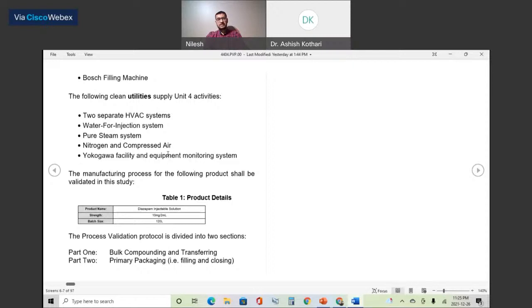This is Yokogawa, the name of the software which monitors 24/7, 365 days, the differential pressure and environmental conditions like humidity, temperature, nitrogen gas pressure, compressed air pressure, everything. Every time you log in, for each 3 seconds you get the results. So if something is out of spec, like temperature not in control, you get an alarm and your machine automatically stops. It will not work unless and until you go back to the normal operational parameter.